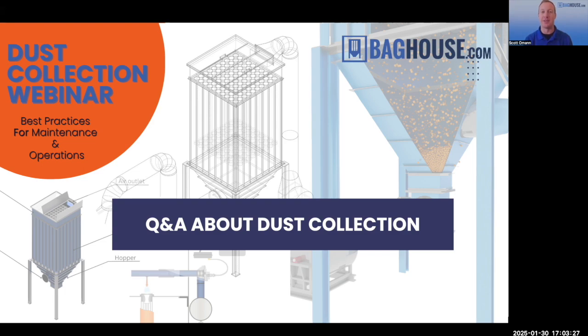And if the dust is accumulating so much within that hopper, it's obviously not allowing the air to go through that airlock to be discharged correctly. So that could be one of the issues right there, right off the bat, as to why the dust collector isn't working correctly. Some places also have so much buildup in the hopper that it's actually pushing the filters and the cages up out of the tube sheet. That obviously is going to be a huge issue. That's going to affect the performance of the baghouse.